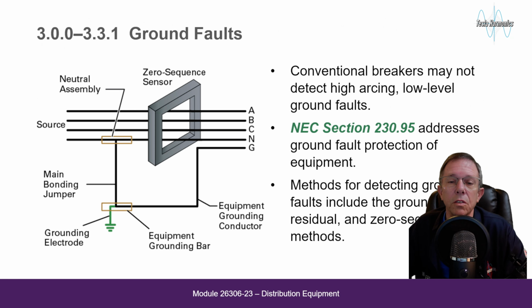Ground faults. Conventional breakers may not detect high arcing, low-level ground faults. NEC Section 230.95 addresses ground fault protection of equipment. Methods for detecting ground faults include ground return, residual, and zero sequence methods. Sensing operation. Under normal conditions, the current from all phases and neutral conductors add up to zero. When any ground fault occurs, the sensor produces a signal.